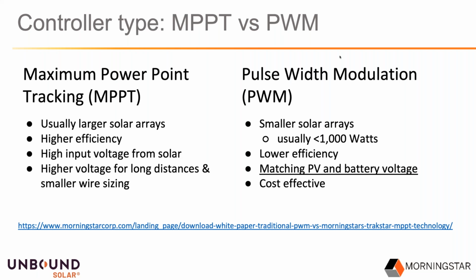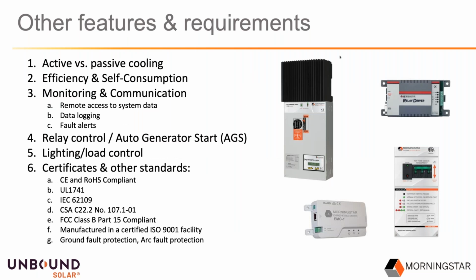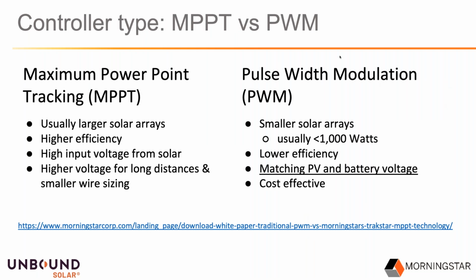The thing that really distinguishes an MPPT controller is the high input voltage from solar. Sorry about that, the cat stepped on the keyboard. You have a higher voltage coming in from solar that gets converted to a lower voltage for charging batteries. An MPPT controller is going to lower the incoming voltage and raise the current proportionally at a very high efficiency, about 99% efficient. Essentially we're coming in with a higher voltage than what we would typically see at the battery charge. This higher voltage is really beneficial for long distances.